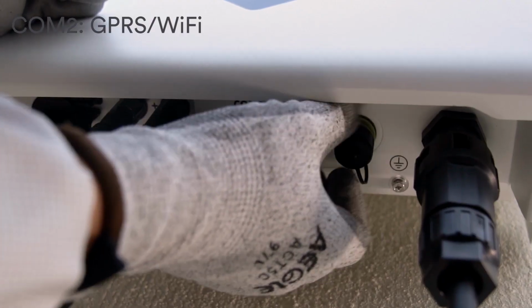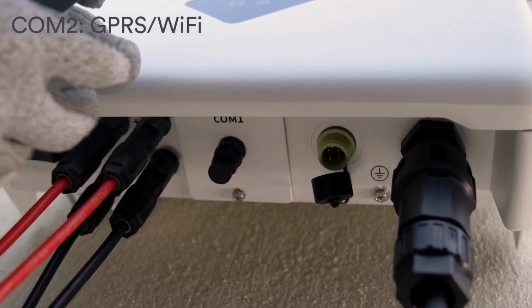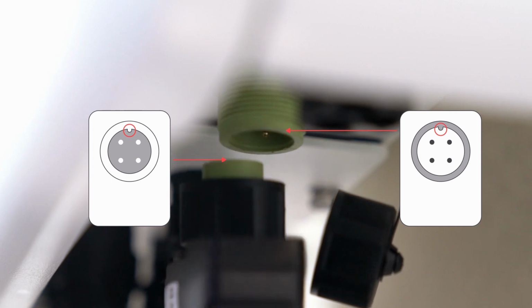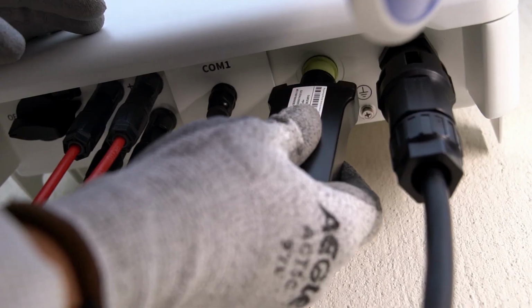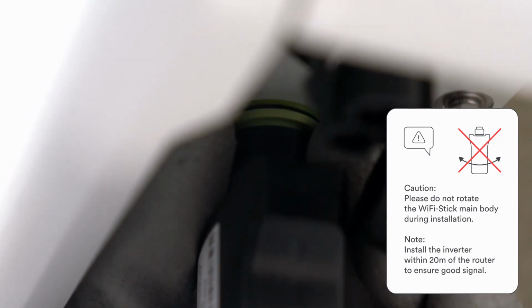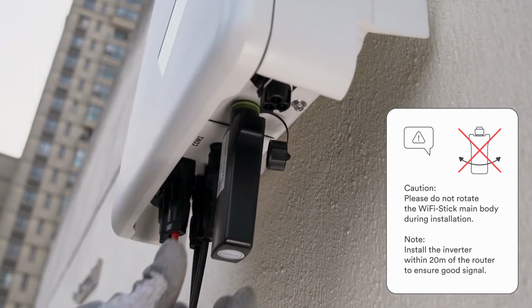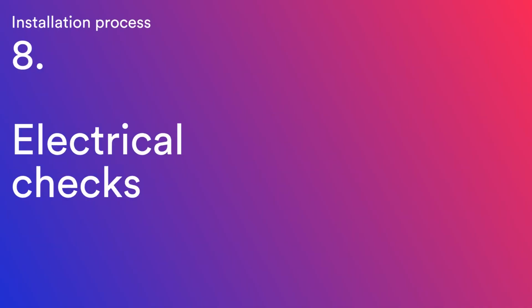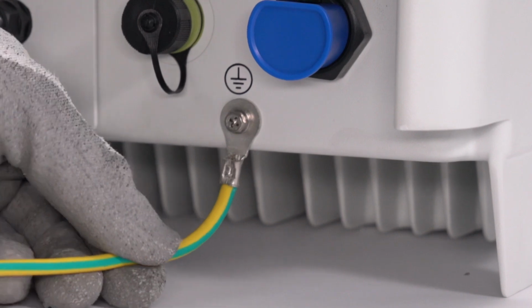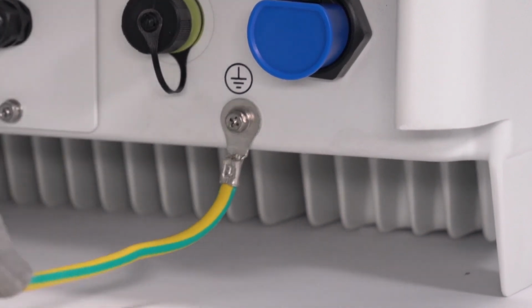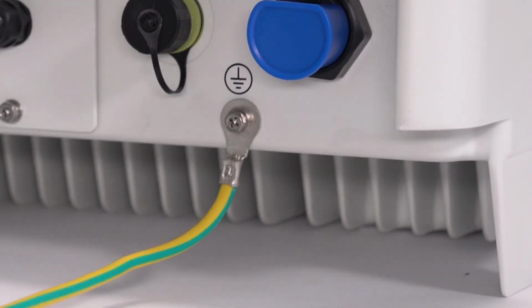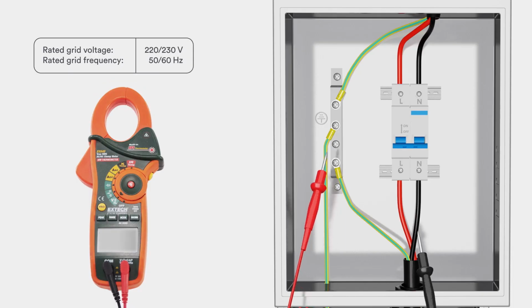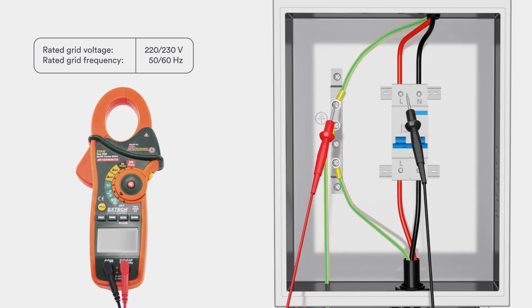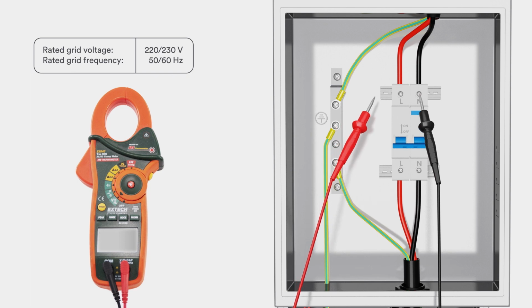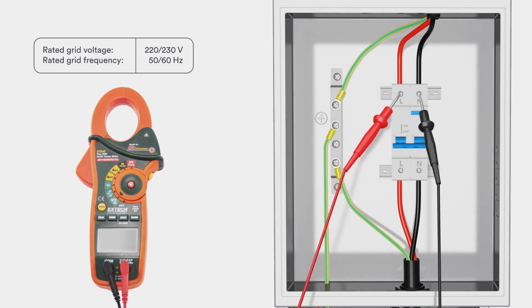Remove the anti-dust cap of the connector on the inverter by rotating anti-clockwise. Insert the GPRS or Wi-Fi stick to the connector on the inverter. Rotate the nut on the stick clockwise and tighten it. Check the PE connection with a multimeter. Make sure that the inverter's exposed metal surface has a ground connection. Check the grid voltage. Check that the grid voltage at the point of connection of the inverter complies with the permitted value.